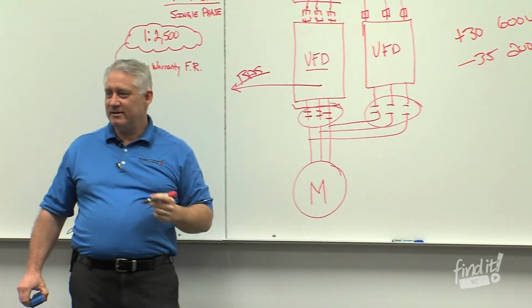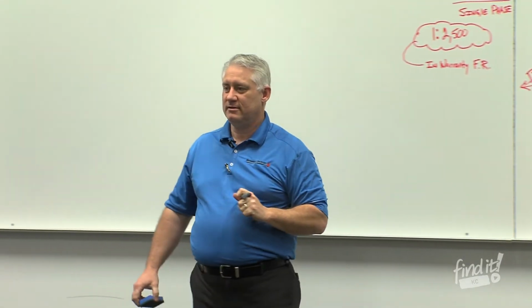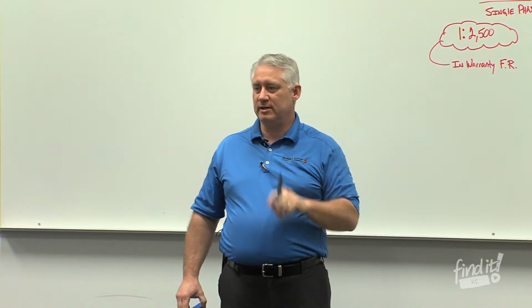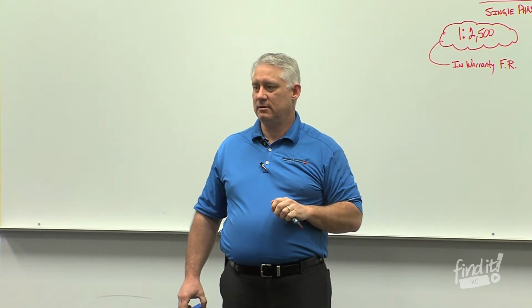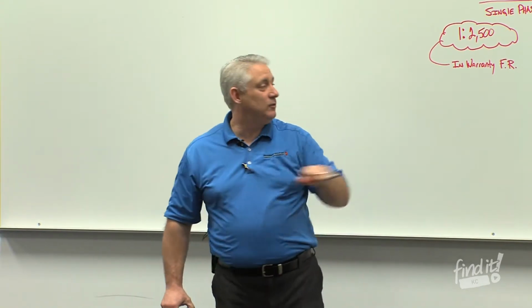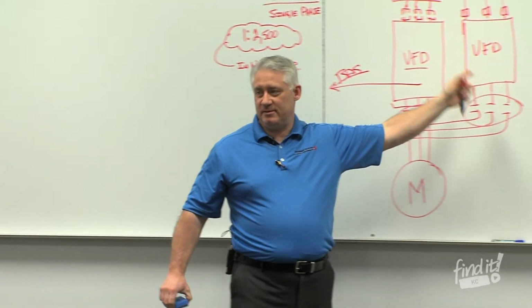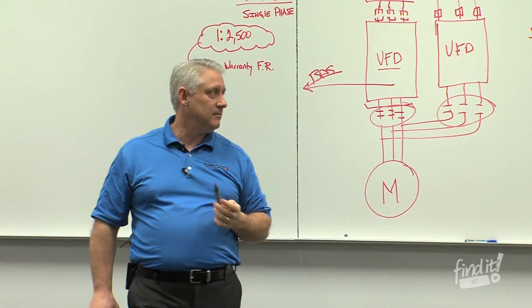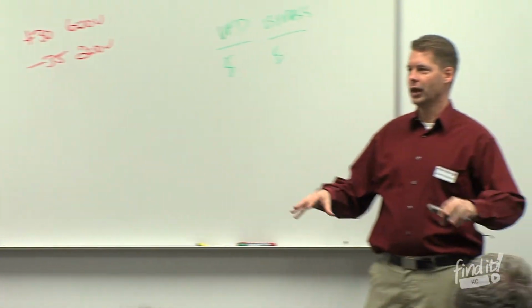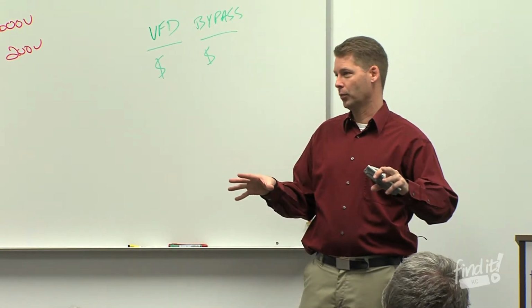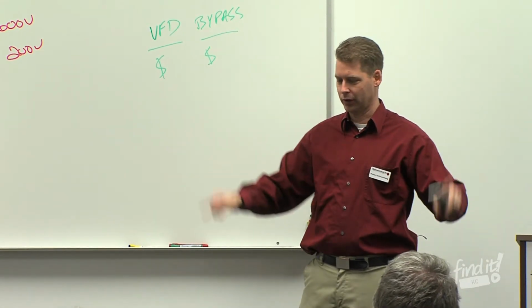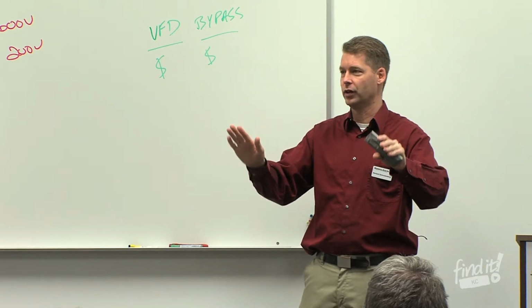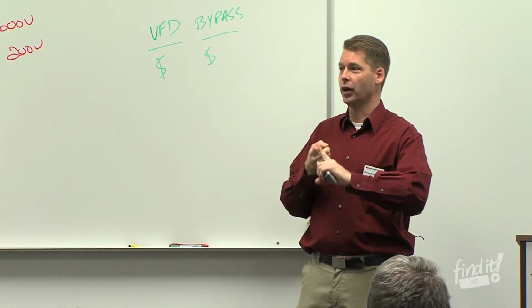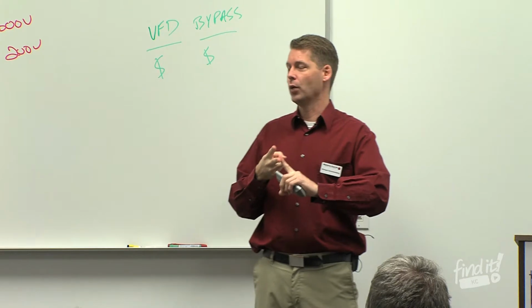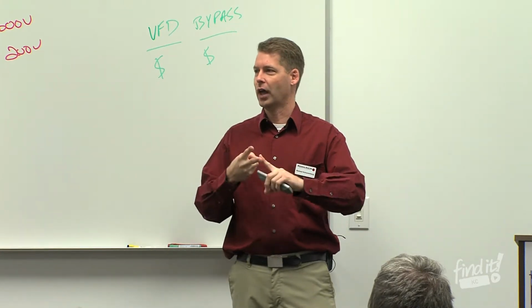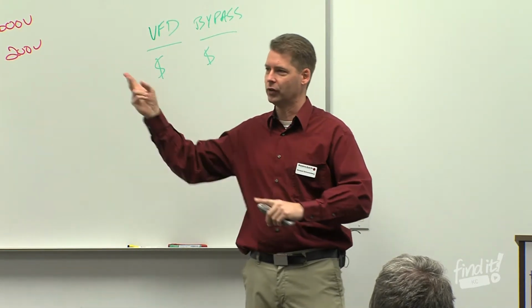Right, but what I'm asking is, if I had a 5 horsepower drive only, and I add the bypass to it, it's double, so I could almost buy two drives for about the same price. You could, but then you still have to buy all the same components in a bypass. Yep, absolutely. So if you had 2 motors and 2 pumps, at 5 horsepower per motor, do I put a drive and a bypass and separate that one to go to both motors, or do I buy 2 little VFDs? Buy 2 little VFDs. You've already got redundant motors and you've already got redundant pumps, so why would you then need a redundant VFD and bypass for each of those? No, just buy a simple VFD only at that point.